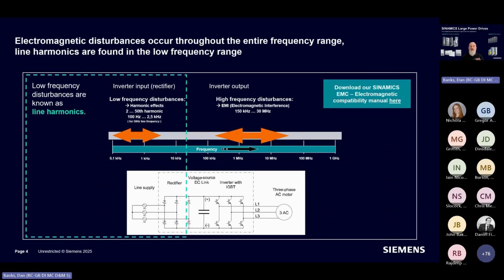Harmonics generate a whole different set of challenges, often associated with interference, but in my opinion that's broadly a 20-year-old view. Back when we had filament bulbs and CRT TVs, harmonics could regularly cause interference - like when someone's lights flickered whenever the water company turned on their pumping station. That's low frequency causing visible fluctuations in electronics. But unless harmonic distortion gets really high, it's pretty unlikely nowadays to cause that kind of interference. I'm not ruling it out, but it's not common.